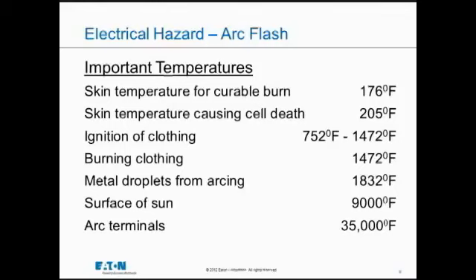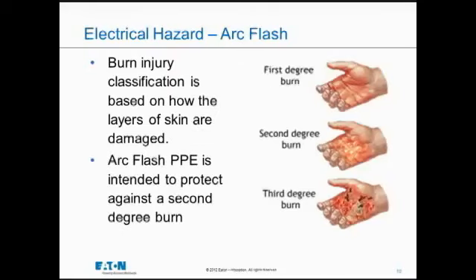What's been decided in best practice is to protect humans from second-degree burns in the workplace. So the protection that is provided for arc flash is intended to provide protection against a second-degree burn. And the hands on the right-hand side are just showing that as the degree of the burn gets worse and worse, we go from first to second and then to third, and there's even a fourth-degree burn.